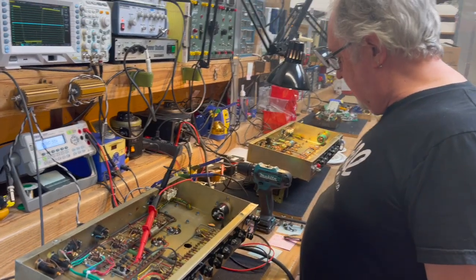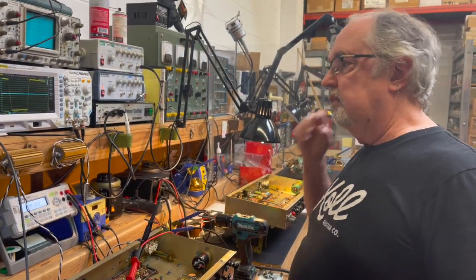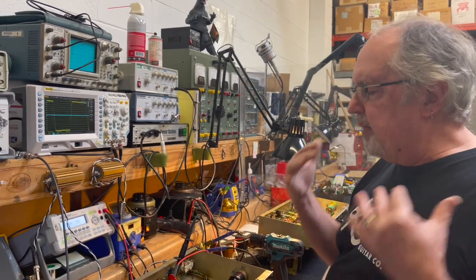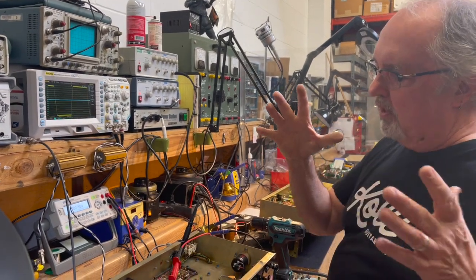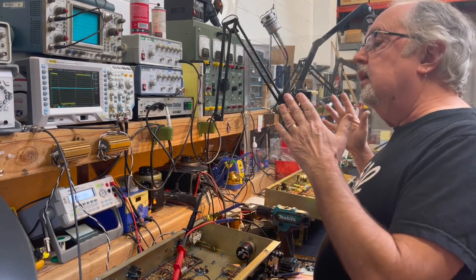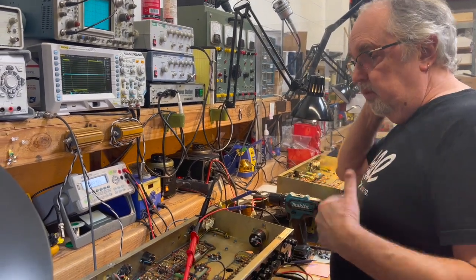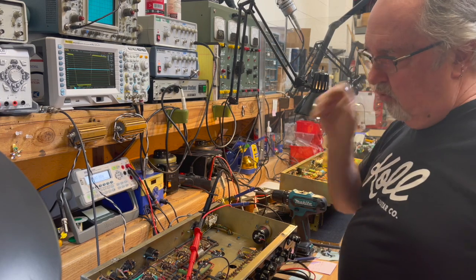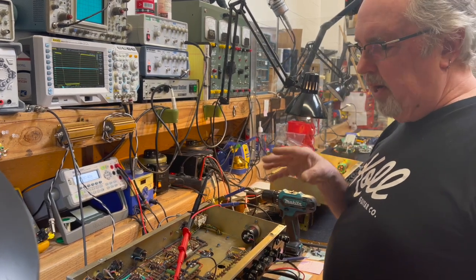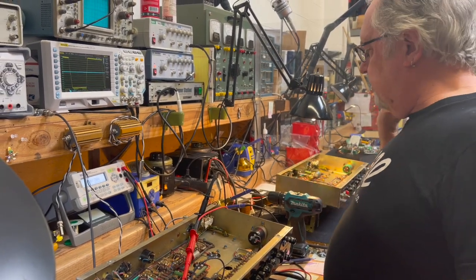The 50 at full saturation was 387. So you see, as the demand on the power supply increases, the difference between the voltage on this one and this one tends to converge, because you're maxing everything out. You're drawing the maximum amount of current out of the power supply that it's designed to produce in both cases.